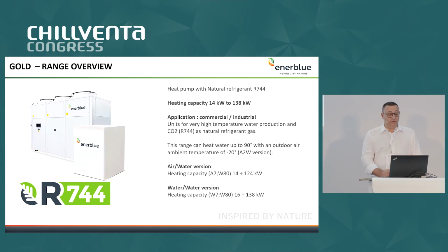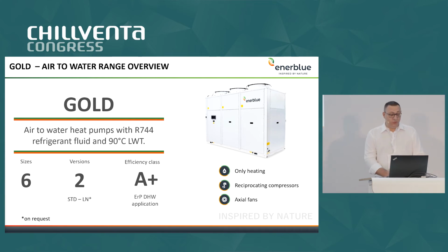Only to give you an overview about the air-to-water version of this unit. So we have 6 models with a heating capacity from 14 kilowatts up to almost 140. Application is mainly for commercial and industrial applications where high temperature water is required. These 90-degree leaving water temperatures are always granted, even if the outdoor ambient temperature is down to -20. There is the base version, the air-to-water version, and it is possible also to have a water-to-water version with more or less the same heating capacity. So we have this air-to-water range, 6 sizes, 2 versions.